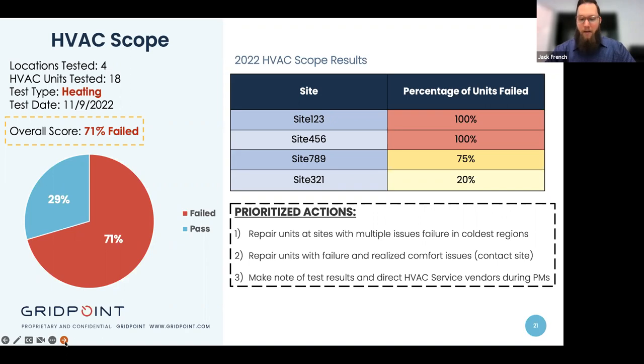So now we have what we talked about earlier: quantified and qualified evidence, but we also have anecdotal evidence that there's a comfort concern there. Then finally, making note of test results and directing HVAC service vendors during PMs. If you're already going to schedule recurring PMs and do fall PMs to get ready for winter, run this report before you do it. That way you have a targeted list of where to focus, because we've run this diagnostic test and we know where you have potential risks for comfort concerns due to unit failures.